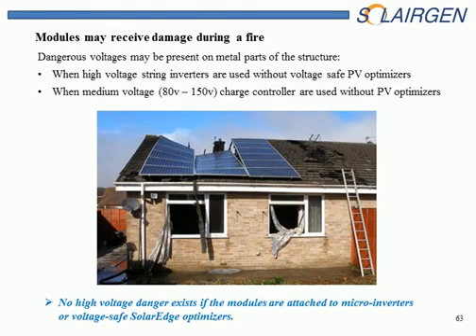In this photo, we're looking at a fire that occurred not because of the PV array, but the PV array was directly involved in the collapse. It was right on top of the fire. In this case, you have another potential. If these were high voltage strings, then you could actually have a high voltage potential while this fire was going on. So that's what we're trying to avoid or find out about.